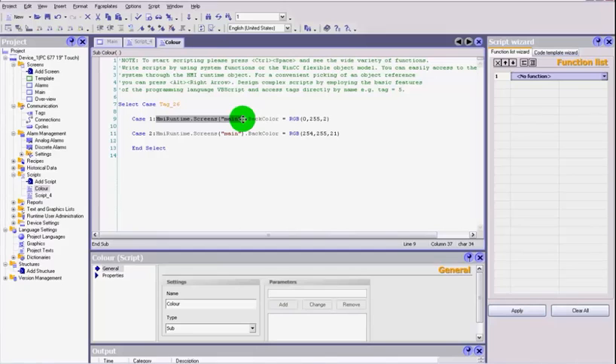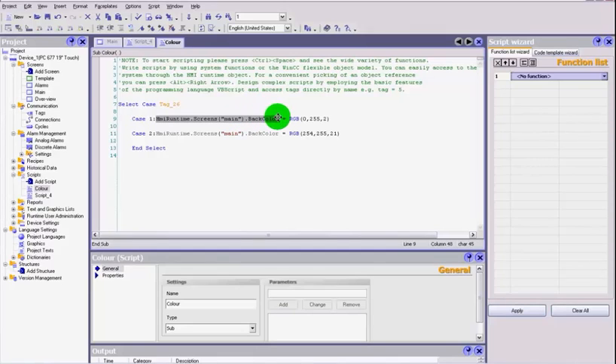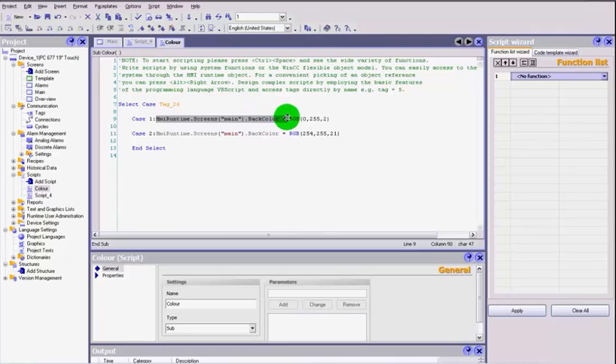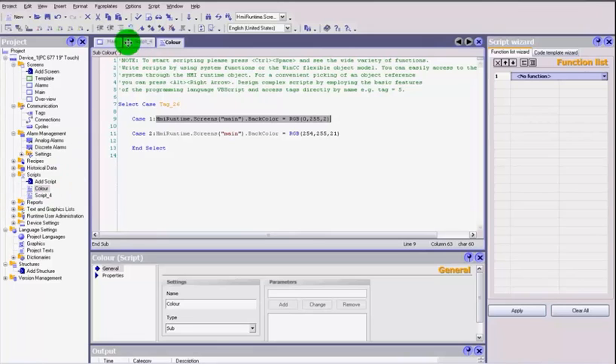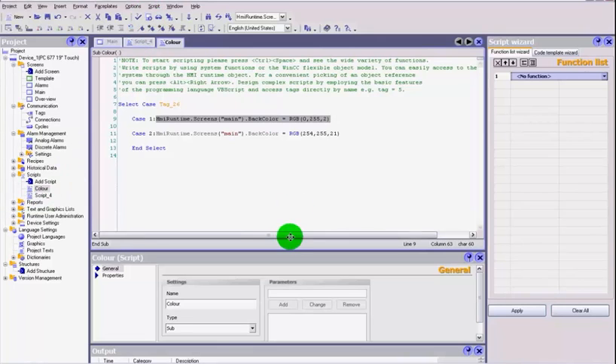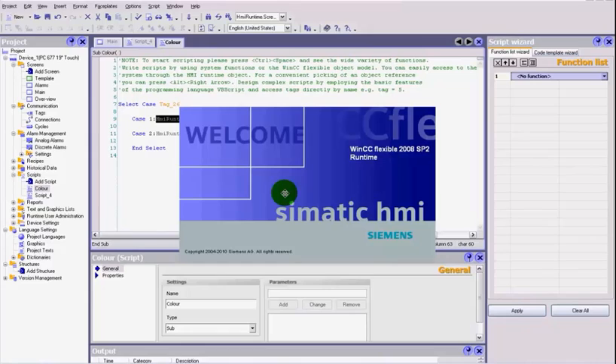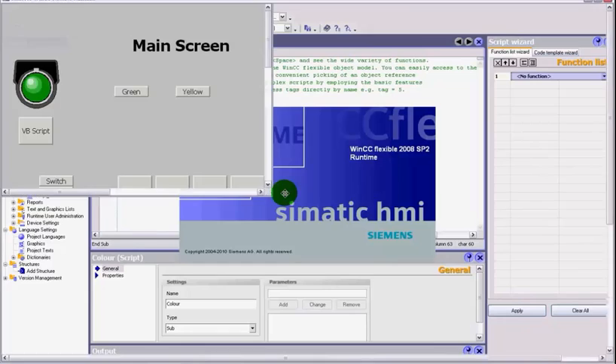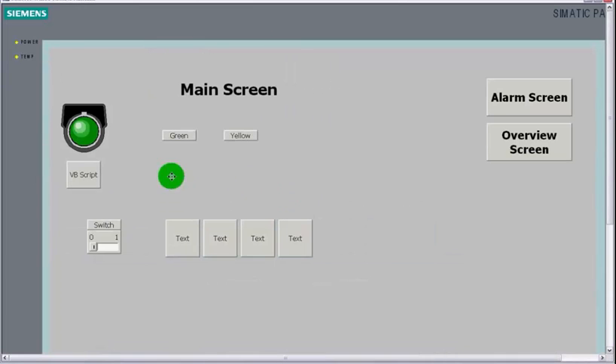So what we're going to do is when that button is pressed, a value is going to be attached to that variable Tag_24. Based on that value, whether it be a 1 or a 2, it's going to select case 1 or case 2, and then depending on which one it is, it's going to select the main screen, select the back color of that screen, and change it to the new RGB value.